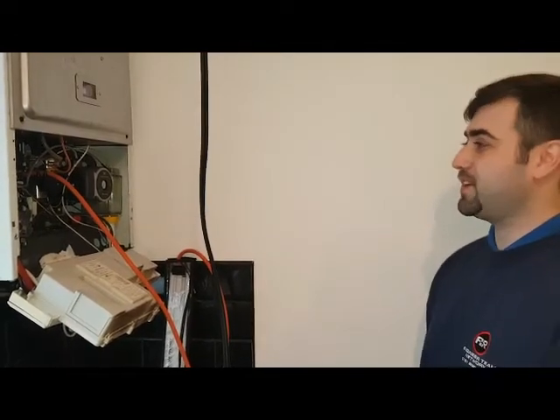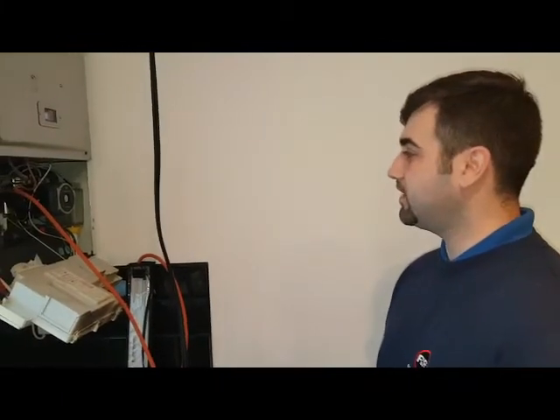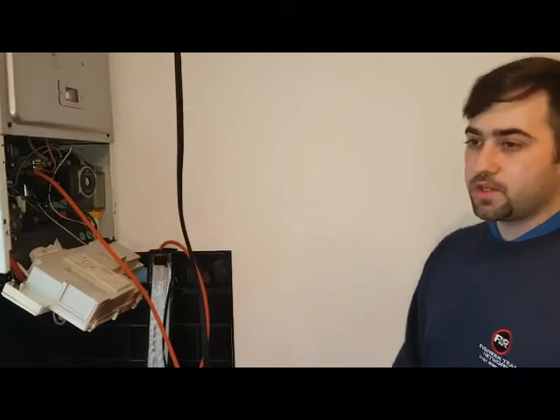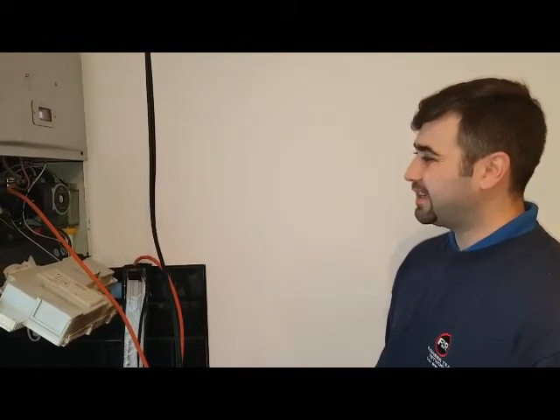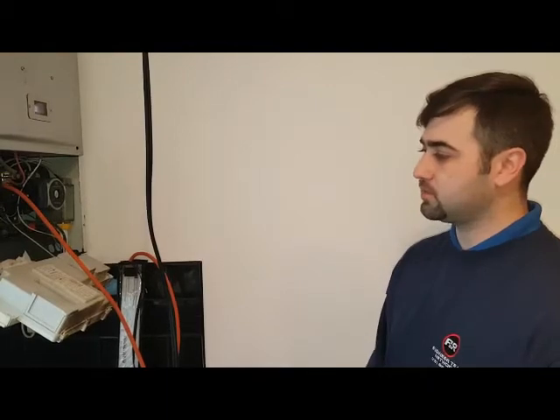It was very short — just a few weeks ago I didn't know anything about boilers. What about the Ideal ISO one? You had a blocked condense, it was igniting very badly at low ignition. Yeah, it was really noisy on the ignition, and it had the condense trap blocked, so basically I removed that, cleaned it out, put it back, and it worked perfectly.